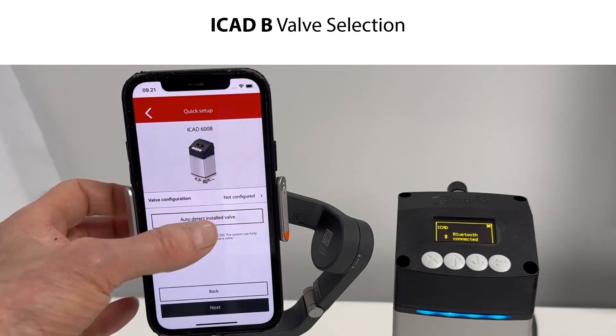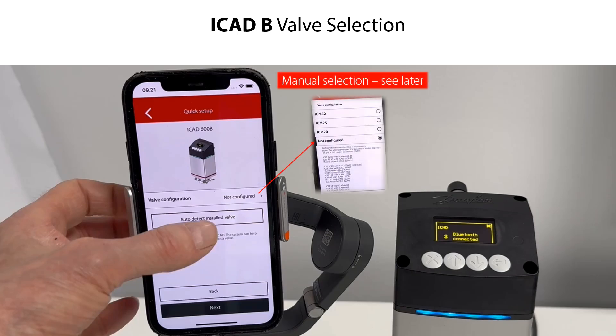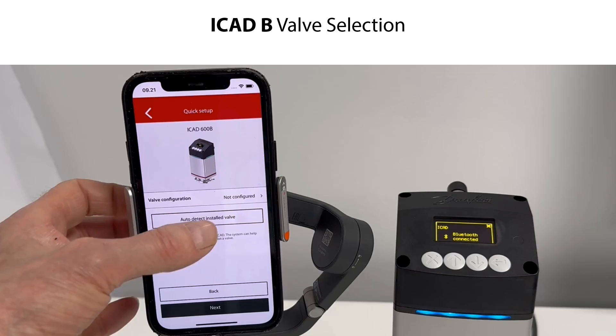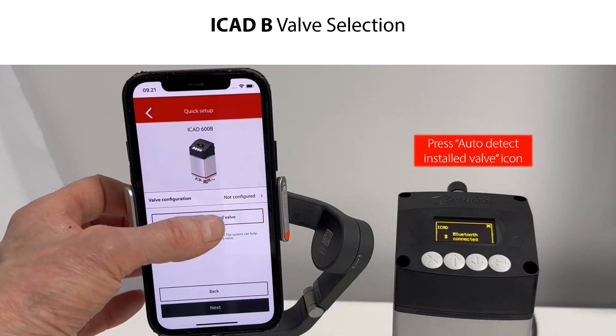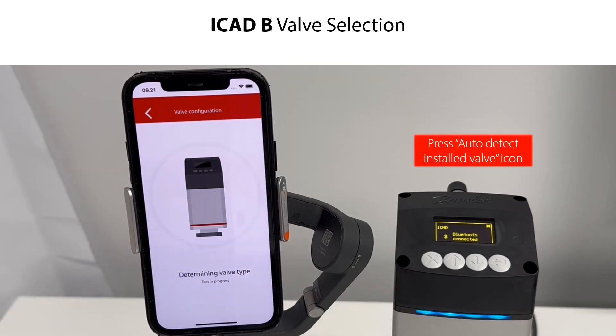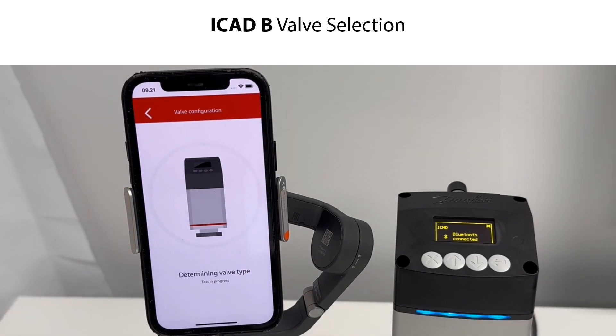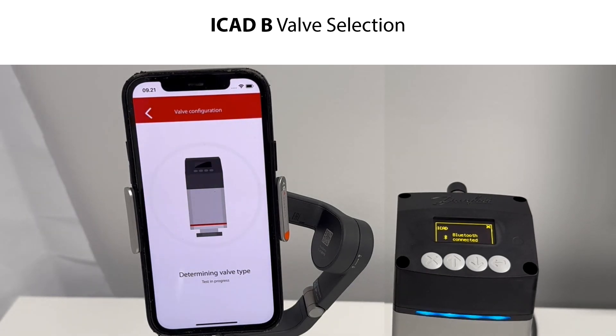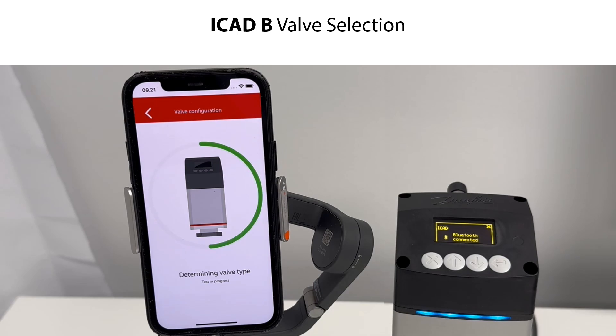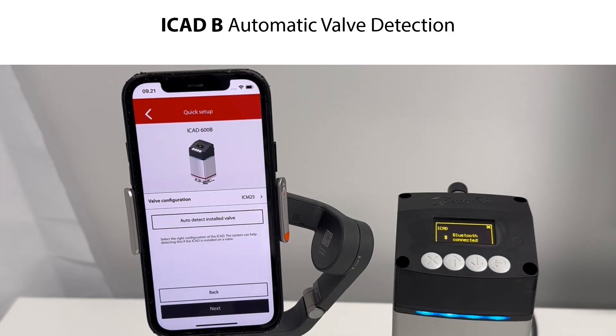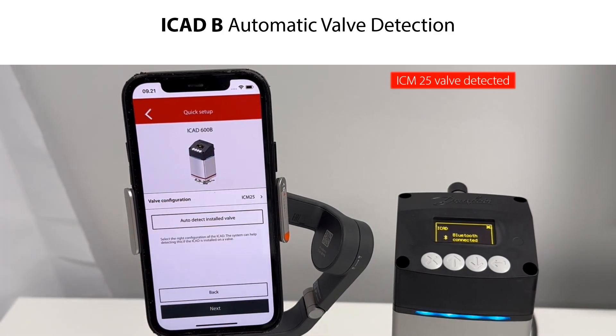You then need to identify and select the valve onto which the ICAD-B is mounted. You can do a manual valve selection, which will be shown later in this video, or you can do an automatic valve detection. In this example, we do the automatic valve detection by pressing the auto-detect installed valve icon. The ICAD-B detects and configures the given valve, identified by a humming noise. The ICAD-B has detected an ICM-25 valve — press Next to continue.